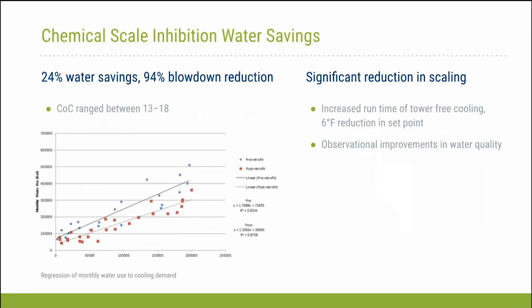So the total savings were similar here. A 94% reduction in blowdown versus 99% in the last one, with cycles of concentration that ranged from 13 to 18. It was my understanding on this one that this had the most scaling of any of the other systems, and so they did have very significant changes in their plate and frame heat exchanger operation.